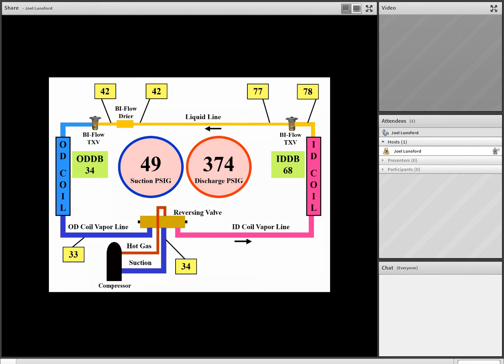Maybe somebody was in the attic and they stepped on the liquid line when they were up there doing a service call or cleaning the coil or whatnot, if it happened to be in the attic. And we see that we've got a huge temperature difference now across the liquid line, and we have a restricted liquid line. Now remember, team, it doesn't matter if you're in the heating or the cooling mode of operation. Any temperature difference, any more than about 6 to 8 degrees across the liquid line, you know you've got a restriction in it. So here we have a restricted liquid line as our diagnosis.